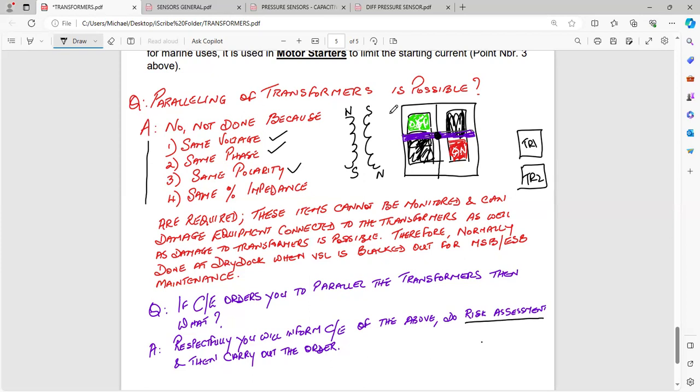Okay, sir. When the ship is completely blacked out, you don't have lights, nothing. So you can very safely do this, no? Switch off there, put this in the on position and switch this in the off position. Done. And you do it both for your main switchboard as well as for your ESB. In your emergency switchboard and emergency generator room, you also have these two transformers, correct? Yeah, so there also don't forget to do this job as well. Okay, sir. Okay, sir.